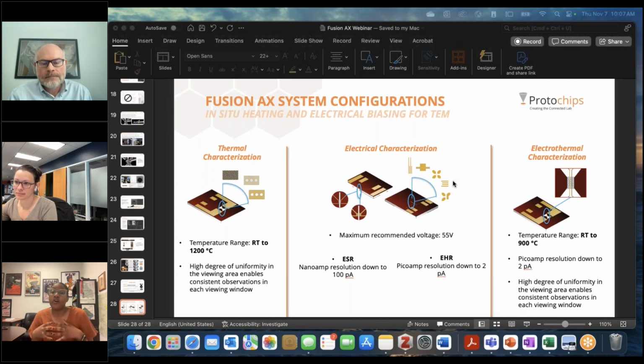And then we offer two different systems for electrical characterization. You can go down to nanoamp resolution or picoamp resolution, and again, it depends on the type of experiments that you want to run. They both go up to about 100 milliamps. With the standard version, which is nanoamp resolution, you can go down to 100 picoamps. But you have even better resolution with the high resolution electrical system that goes down to 2 picoamps. So it really depends on the customer, what they decide is best for their experiments, the type of sample, and the type of experiments they want to run on the options that they have.